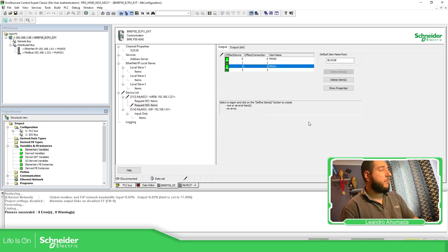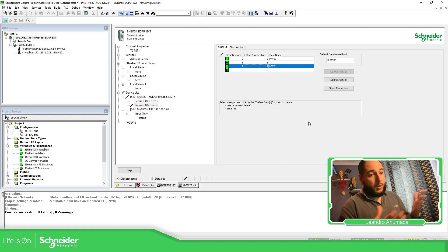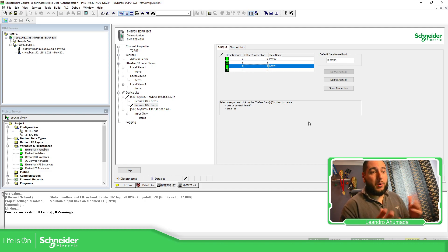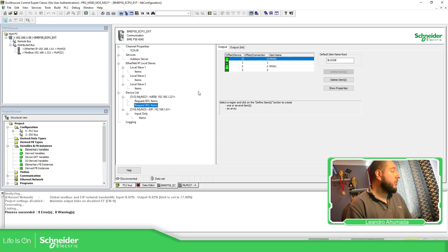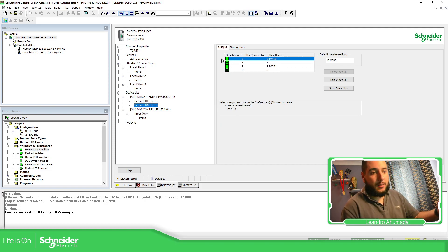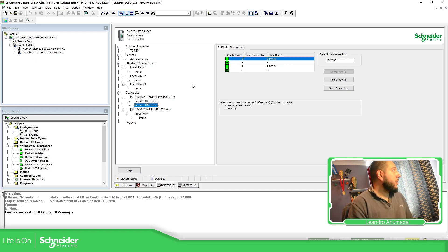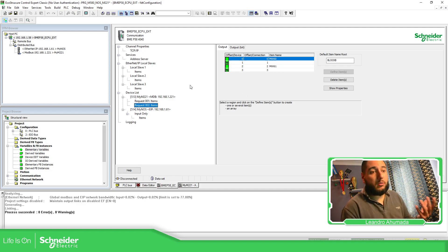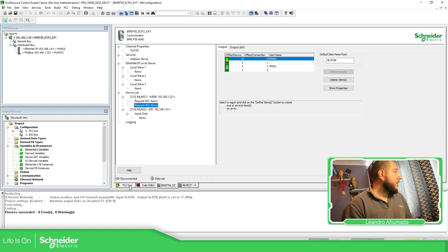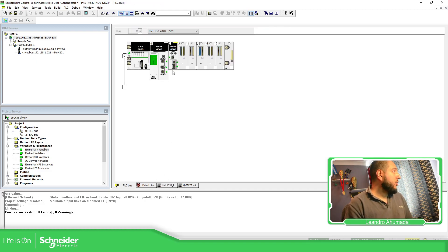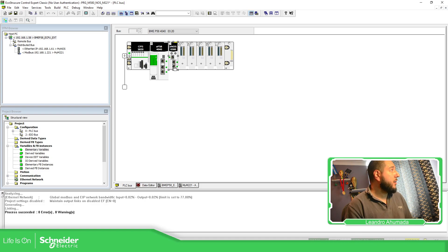If you're using all the type of variable, then you can probably use, for example, reals, you just need to read two words and then make the conversion inside the software. Remember that we just read words, then we just need to translate that into the right variable type. So now that we have this, we should be able to connect to the M580 and then directly to the M221. So how is my connection right now? I have my USB cable connected to the USB port. And then I have the M221 connected to this one.